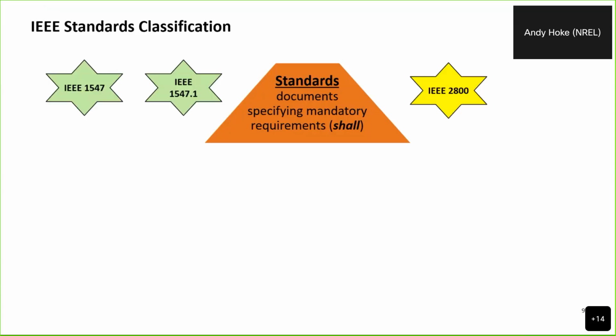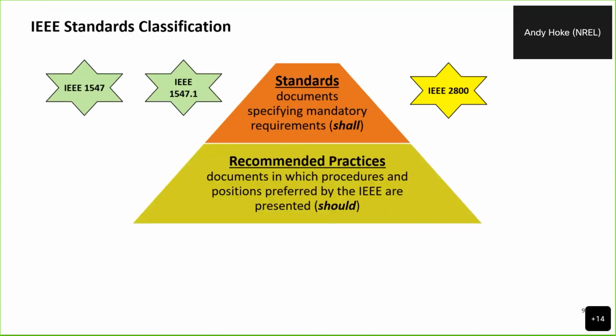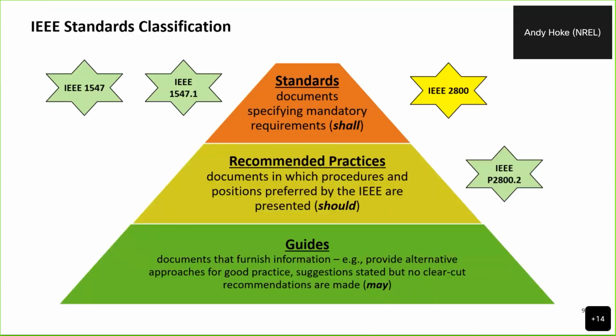A little bit of background information on IEEE standards. Many of you might be familiar with this. IEEE creates standards, recommended practices, and guides. 2800, like 1547, is a standard, which means it uses shall language. In other words, it puts out requirements for actual interconnection of IBRs. This is in contrast to recommended practices, which use should language, and then guides, which are things like application guides and use may language.